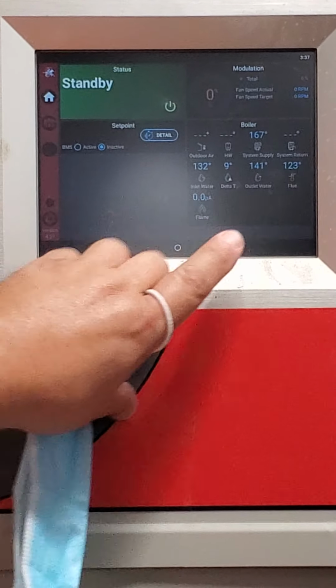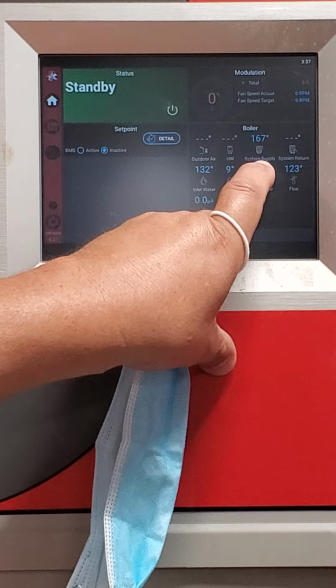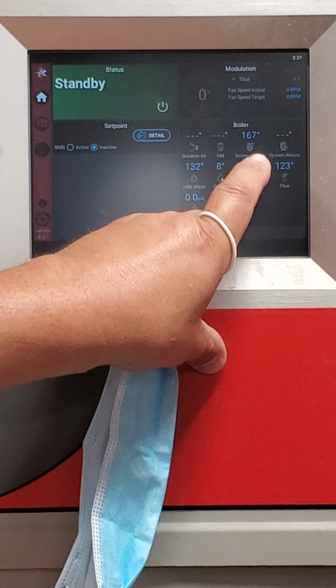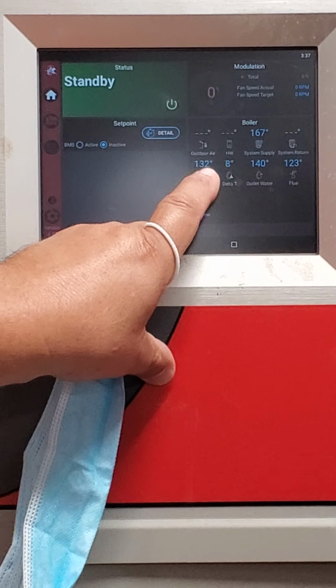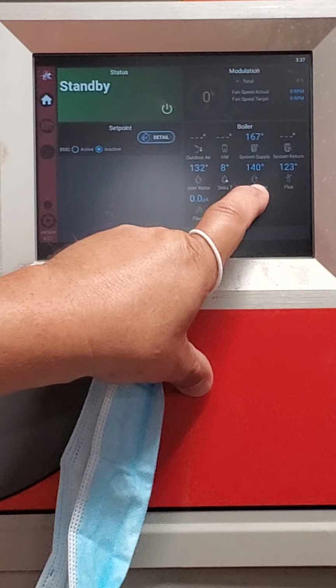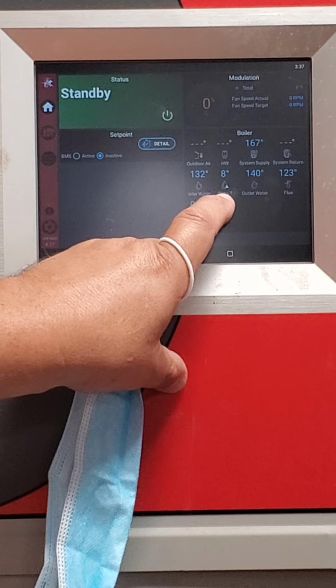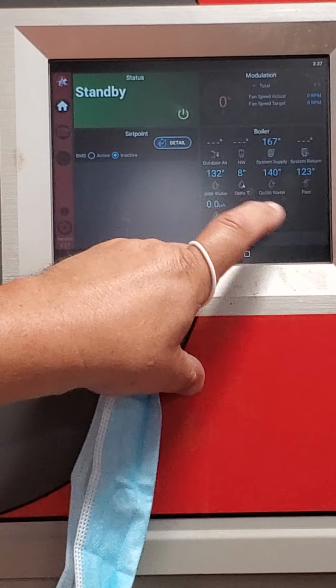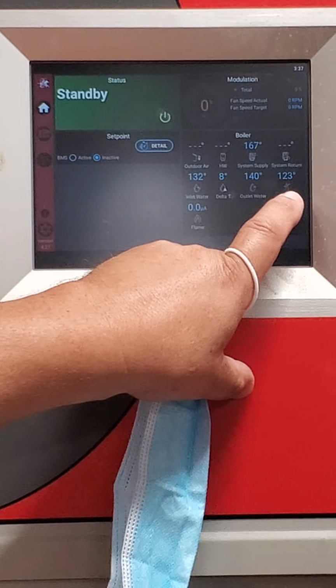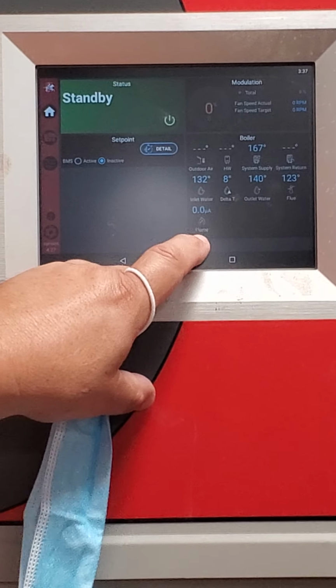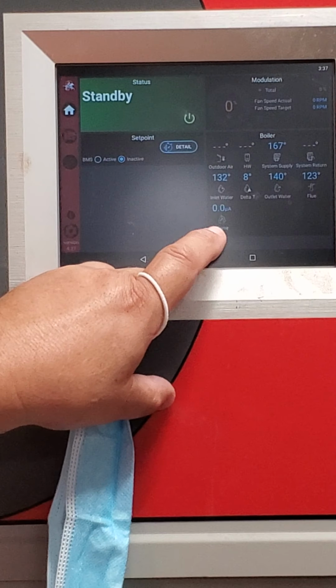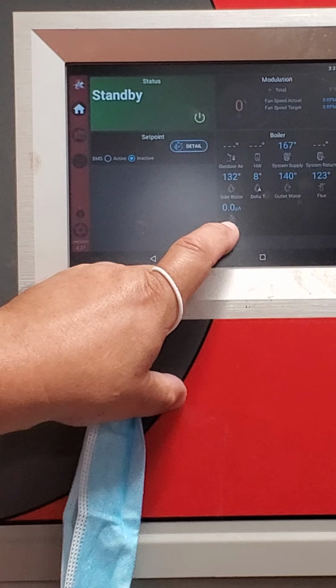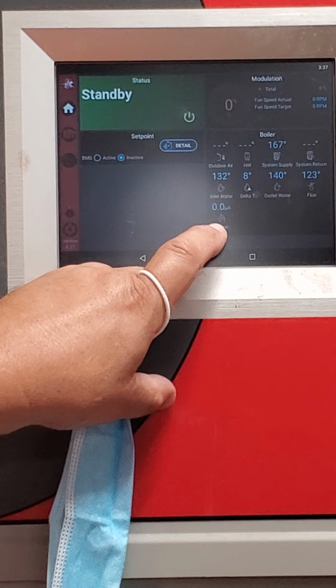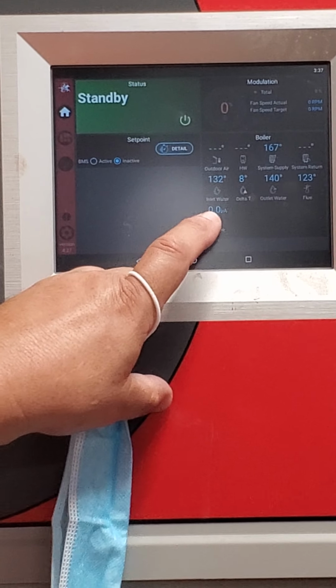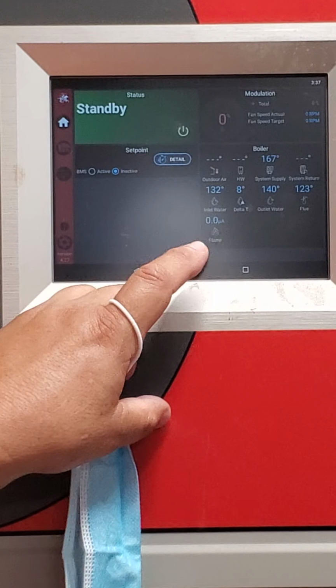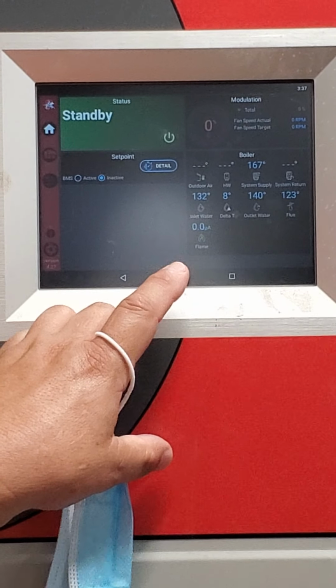There's information here that you can read. You can see the system supply temperature, 167 degrees. The inlet water is 132. The outlet water is 140. There's a current delta T of 8 degrees through the boiler. It'll tell you your flue temperature and the flame signal if the boiler is running, what the flame signal is. This can vary anywhere between 8 microamps up to about 14 microamps. Average is around 10 to 11, depending on if it's high fire or low fire.